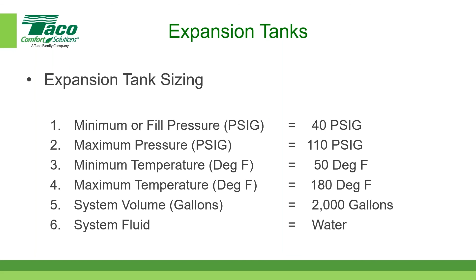And then you can go to our tank sizing app right on our website. You fill in that information, and it brings in a bunch of selections for you. I am at our TACO website - I will go to selection tools, and hopefully some of you have seen this before. One of them is expansion tanks, and there's that - I ran through that screen very quickly, but here's the app we need to fill in, and it gives you some ideas over here. You can actually change the pipe material - personally, from a conservative standpoint, I leave it to copper because it adds a little more flexibility to the system, though I probably should use it the other way around. Then you would need to change your system fluid - very, very important. So let me put in those numbers that we were shown there.